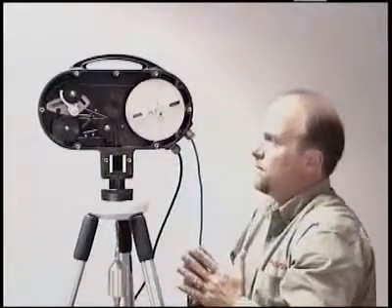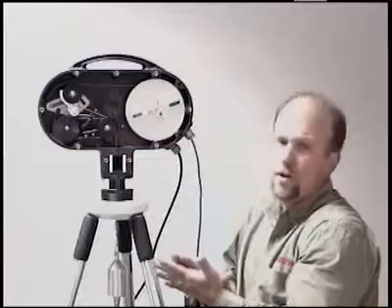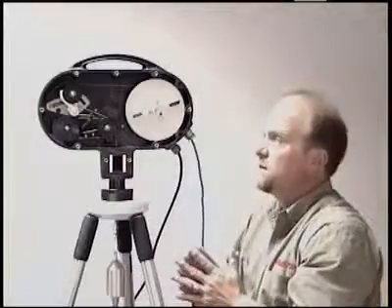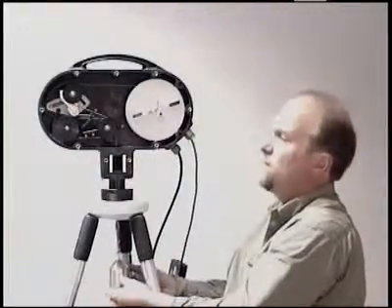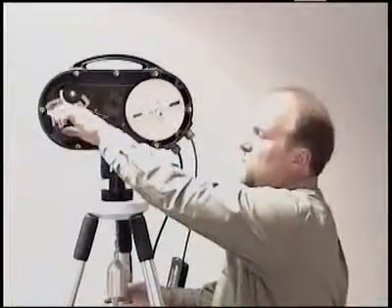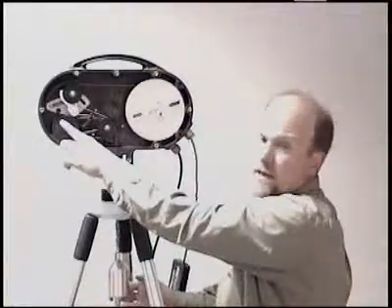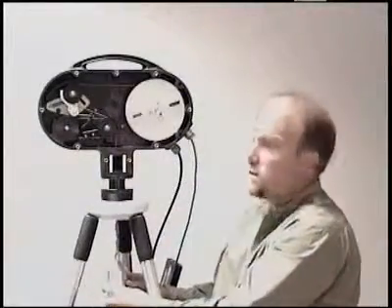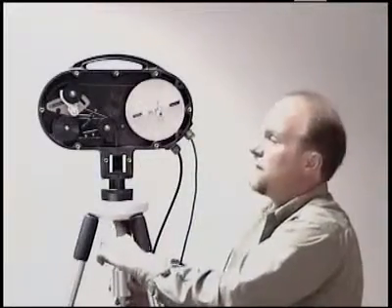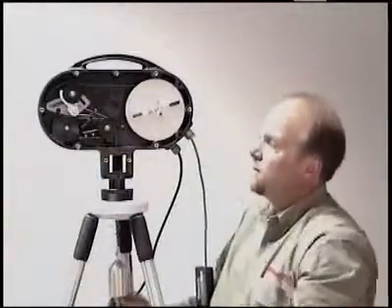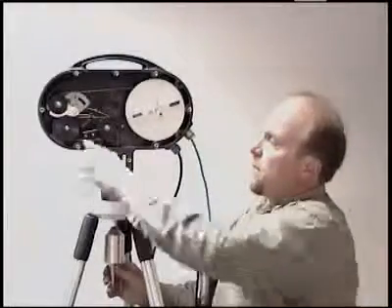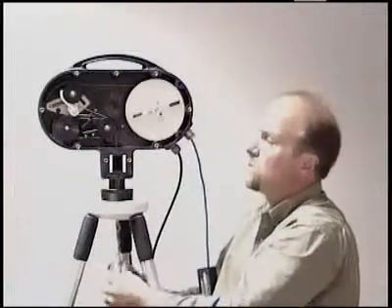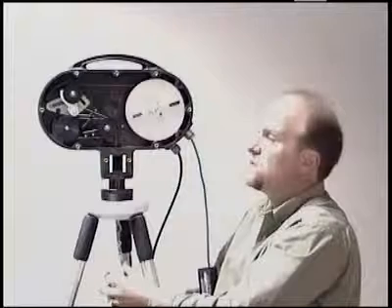If we were measuring material with a high angle of repose or during the fill cycle, or if this bob ever sunk in really light material, enough weight would be taken off that this idler arm would come all the way back and break the timing pulley, which stops the motor, reverses it, and pulls the sensor probe back up. And this is all done instantaneously.